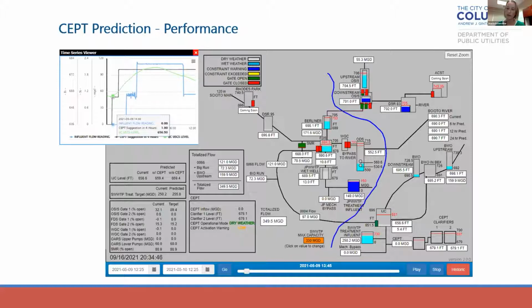We want it to look like something they're familiar with, and this was one of their decisions. This way, operators at each facility would have some familiarity with what they were looking at, which leads to them using it more. This screen can be displayed in real-time mode, or it has a historic mode where you can go back and look through past events and see what everything in the system was doing, to get an idea of what we do and how we adjust our system during wet weather events.